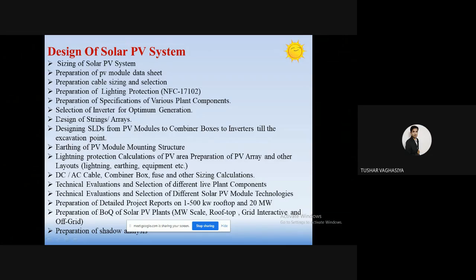One part is the designing of the string and array, as I already told you about different types of solar power plants — string and array. If a number of modules are connected in series, it's called a string. A number of strings connected in parallel is called an array. How to size — how many modules to connect in series, how many in parallel — depends on the particular rating of the solar module as well as the inverter module.